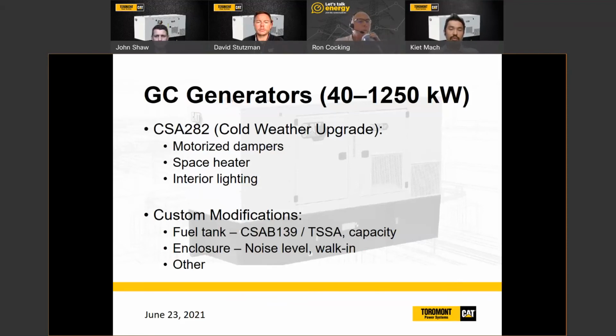We also talked about the enclosure. The ones from Caterpillar are generally 75 decibels at 7 meters or quieter, and if those suffice, we'll use those. Otherwise we offer our own customization, or we can build a custom enclosure with walk-in capability, or even lower sound level outputs, going down to 50 or 55 decibels at times.